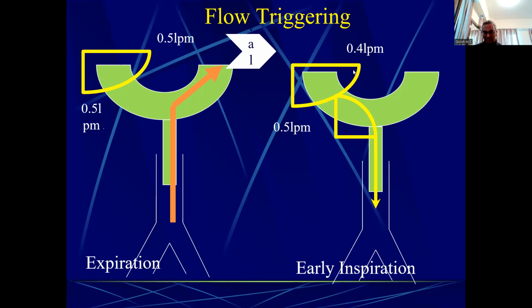And once it senses, what does the machine do? It closes the exhalation valve. It closes the exhalation valve. Once the exhalation valve closes, machine gives a big breath, whatever you have set. So this is how the flow triggering works. So obviously you can see this is much more complicated, more technology is needed. So that is why it is a little more expensive, but most of the modern ventilators incorporate that.